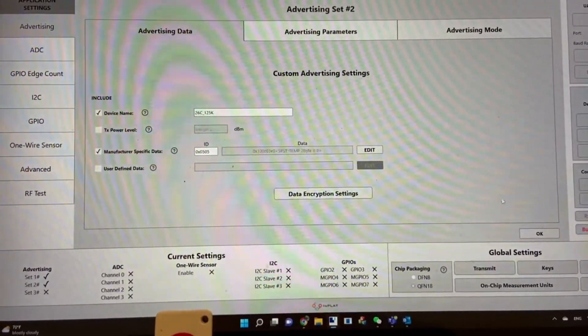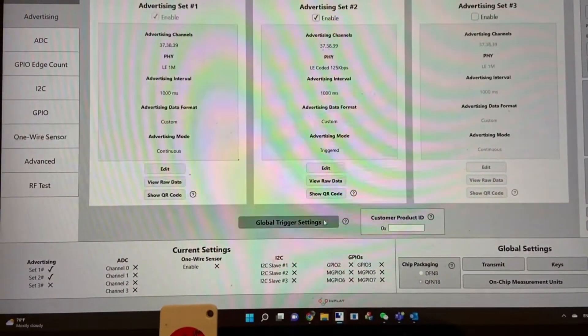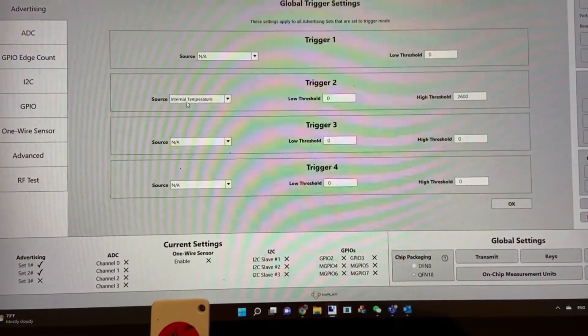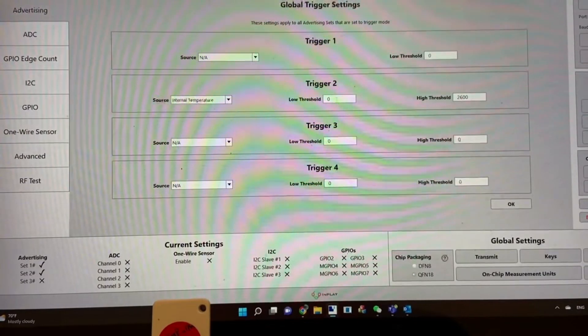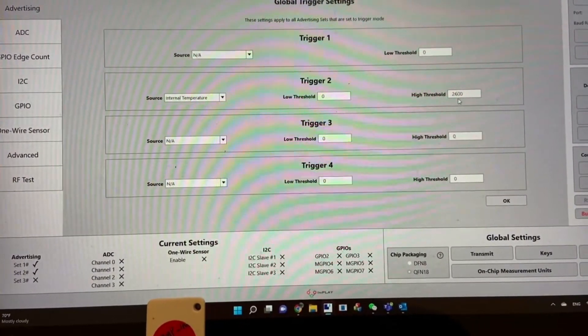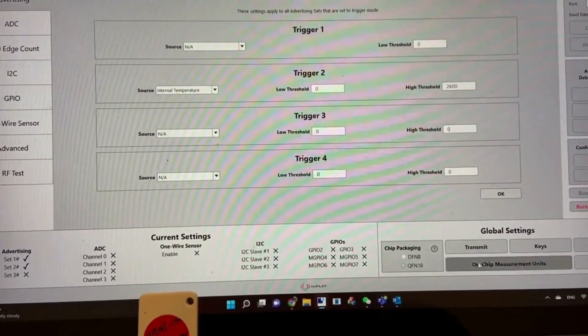I put the trigger condition as 26 degrees C. If you go to global trigger settings, you see the trigger source is internal temperature sensor and the high threshold is set as 2600.